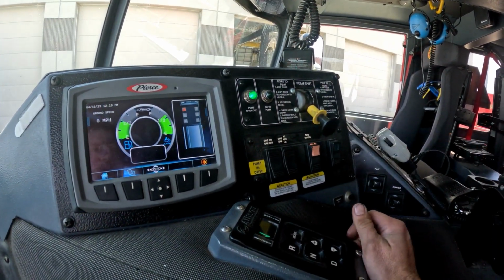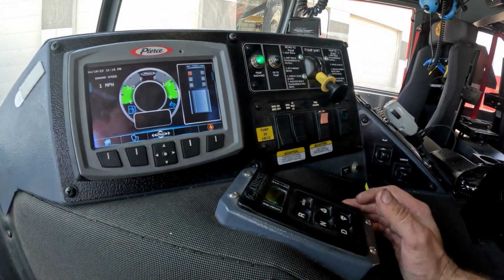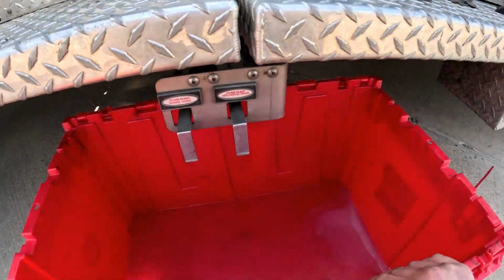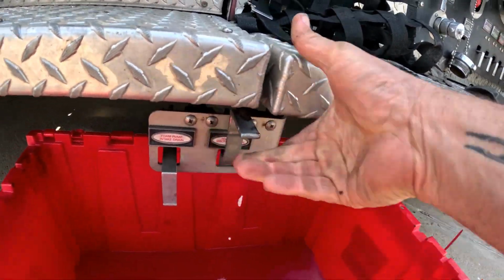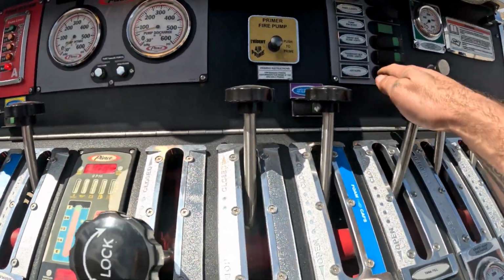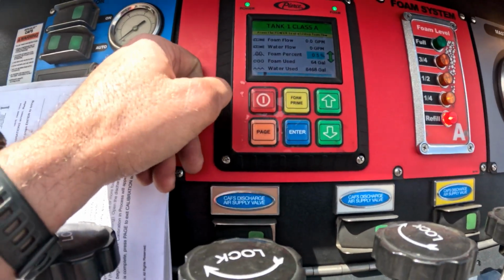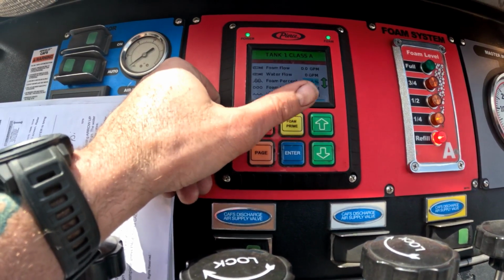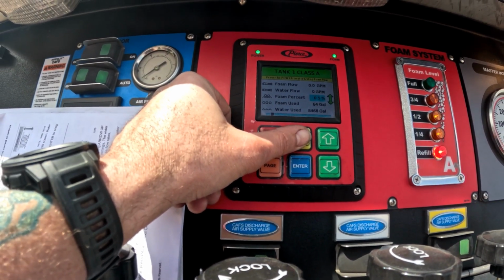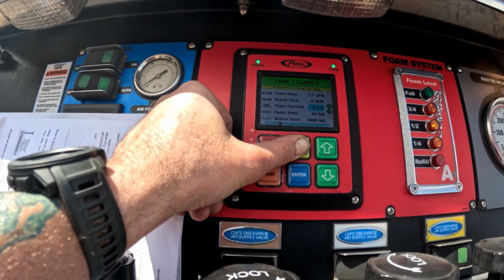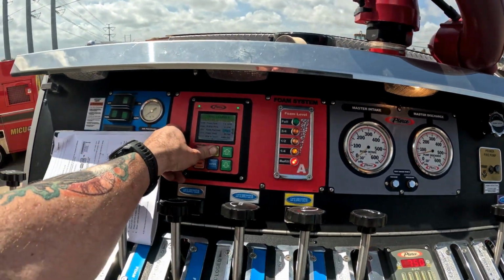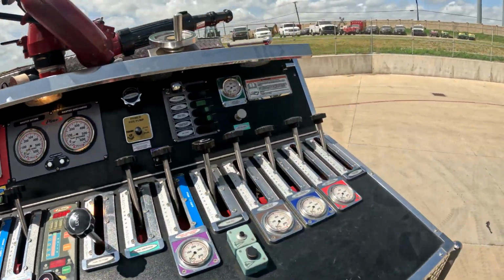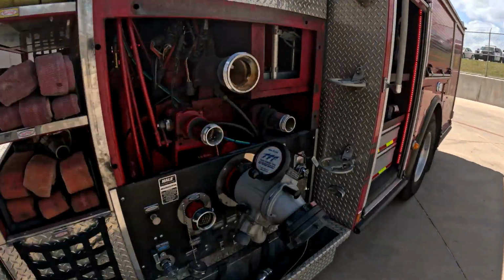All right, so first thing I'm gonna do is we can probably just do this later, but I'm gonna go ahead and do it right now so I don't forget. I'm gonna go ahead and prime the foam pump. So I'm gonna go ahead and put the apparatus in pump mode. Pump and gauge light is on. I'm gonna put it in drive. So I'm gonna open up the foam pump discharge drain. Tank to pump needs to be open. Tank fill, crack. We're gonna turn on our Pierce Husky 12 foam system, and then hold down this primer button. You can hear it purging. I actually need 2 people to kind of do this, so I'm gonna set you guys down and I'll show you. We should be getting purging out of, yeah, we are.